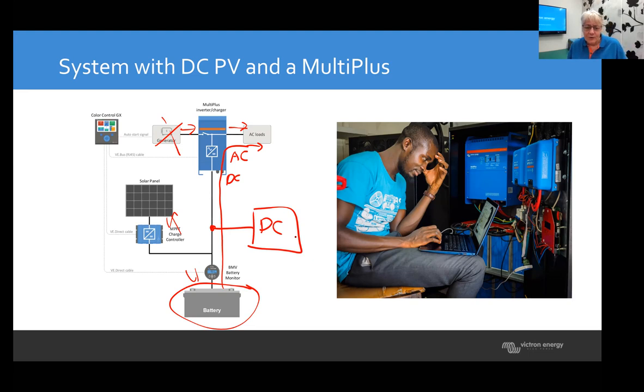The MPPT has a VE.Direct or VE.Can connector, depending on which MPPT you use. The battery monitor has a connector, and the inverter charger has an RJ45 connector, a VE.Bus connector. All this information goes to a central monitoring device, like the Color Control GX, or any of the other GX devices, so you can see your whole system.